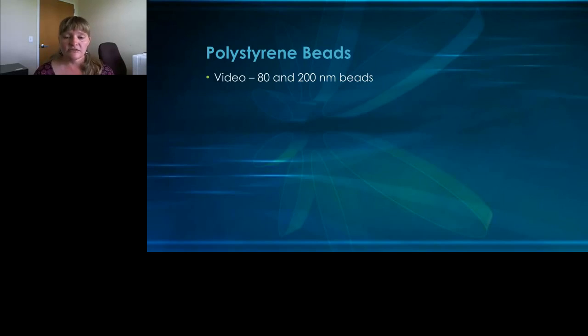Defining instrument calibration standards helps determine flow cytometry's small particle performance. There are 4 different areas I will discuss today: polystyrene beads, liposomes, purchased exosomes, and the electronic pulsar. Each of these standards can be used to determine if the flow cytometer can measure and see EVs. Running polystyrene beads for initial determination of optical sensitivity to EVs is a good start. As seen in the next video after this slide, the Astrios EQ could detect 200 nanometer beads with 80 nanometer beads near the noise floor of the system.